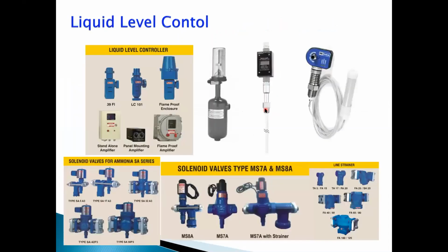As I was talking more and more about level control, I said we use level control. Different types of level controls and solenoid valve schemes are used. You can have a float chamber and electronic controller. The float chamber will generate an inductive signal which is sensed by the controller and gives a signal to operate your solenoid valves, or it can operate your alarms.